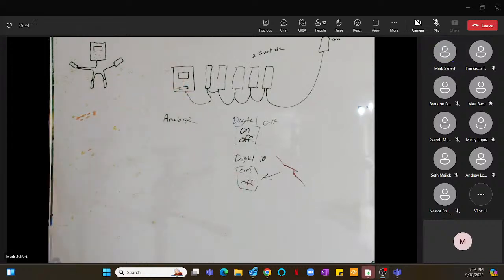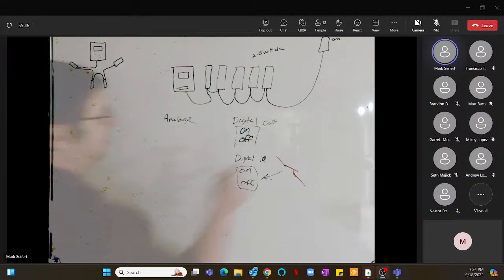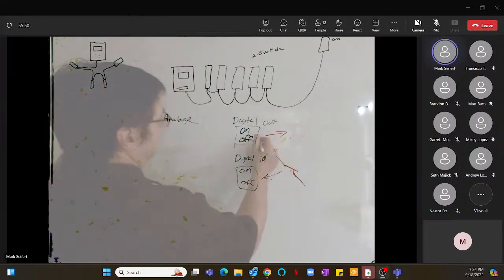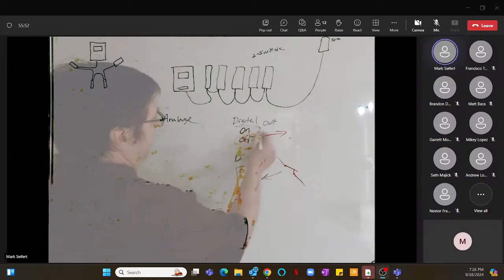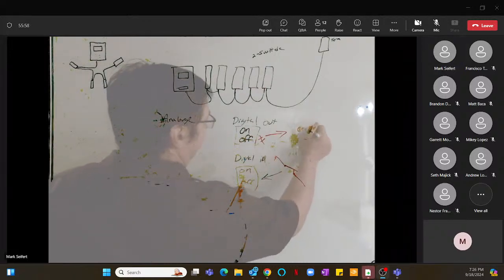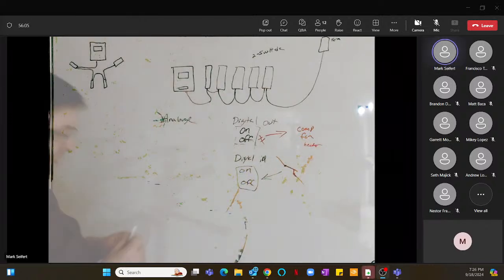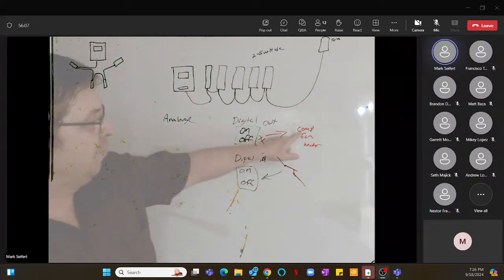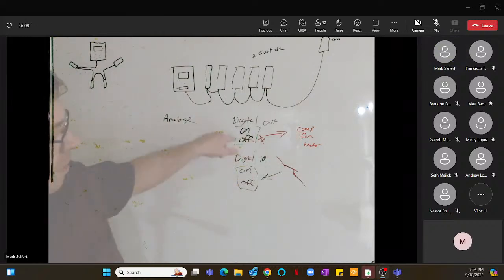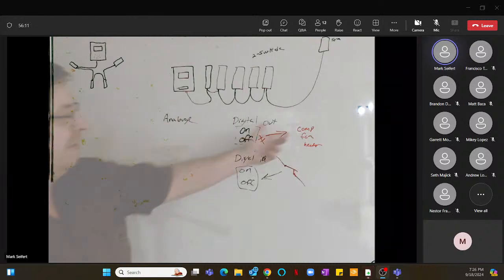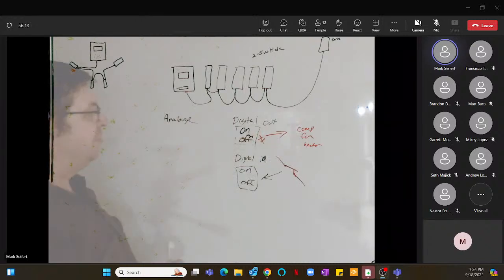Very simple. Digital out, same thing. That's just going out, turns on something. So on would be a closed relay. Turns on compressor, fan, heater. Obviously we wouldn't run a compressor through there because the amps are too high, so this would all be on a contactor, as we all know.